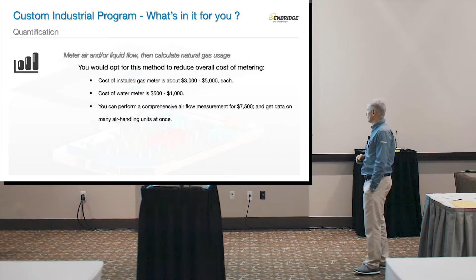If you can't measure the energy driver, you can use a virtual meter, and you need to submeter the data on the boiler or some piece of equipment you can't calculate. There are two ways to measure it: an inline meter, like your typical house meter where the pipe stops, the meter goes in place, and the pipe continues out, or an insertion meter, where the meter gets inserted into the pipe.